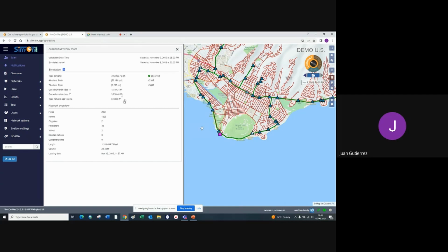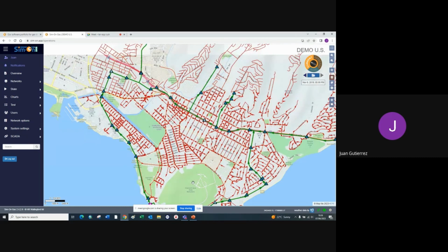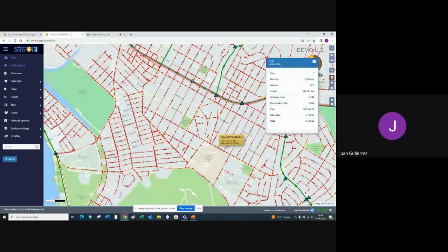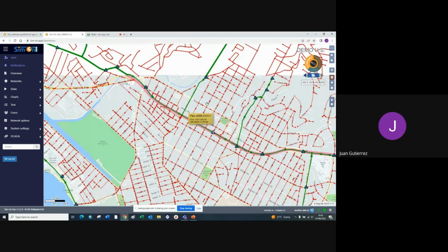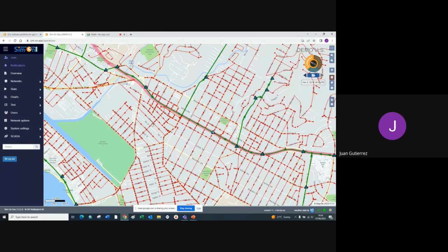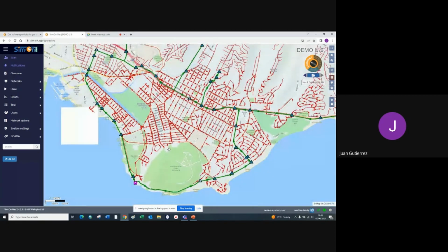And what's the beauty of this? You give me a few sensors and I give you a few SCADA points, and I give you a virtual SCADA system where in each pipe of the model, I can know flow velocity, or in any node of the system, I can know the pressure, okay, and where the gas comes from, for example.